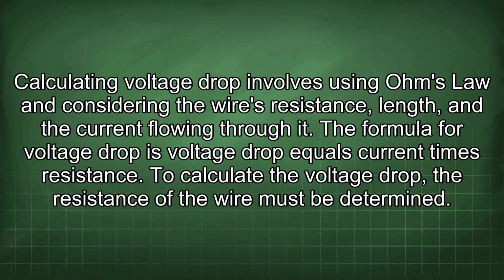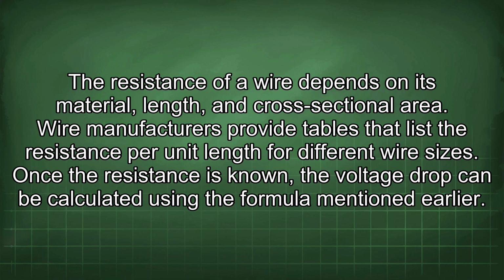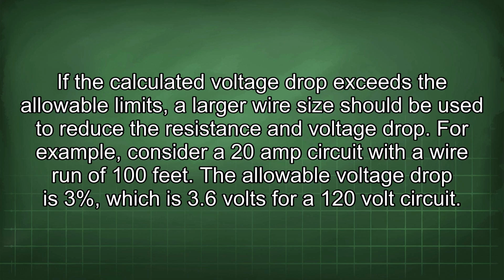To calculate the voltage drop, the resistance of the wire must be determined. The resistance of a wire depends on its material, length, and cross-sectional area. Wire manufacturers provide tables that list the resistance per unit length for different wire sizes. Once the resistance is known, the voltage drop can be calculated using the formula mentioned earlier. If the calculated voltage drop exceeds the allowable limit, a larger wire size should be used to reduce the resistance and voltage drop. For example, consider a 20 amp circuit with a wire run of 100 feet. The allowable voltage drop is 3%, which is 3.6 volts for a 120 volt circuit.